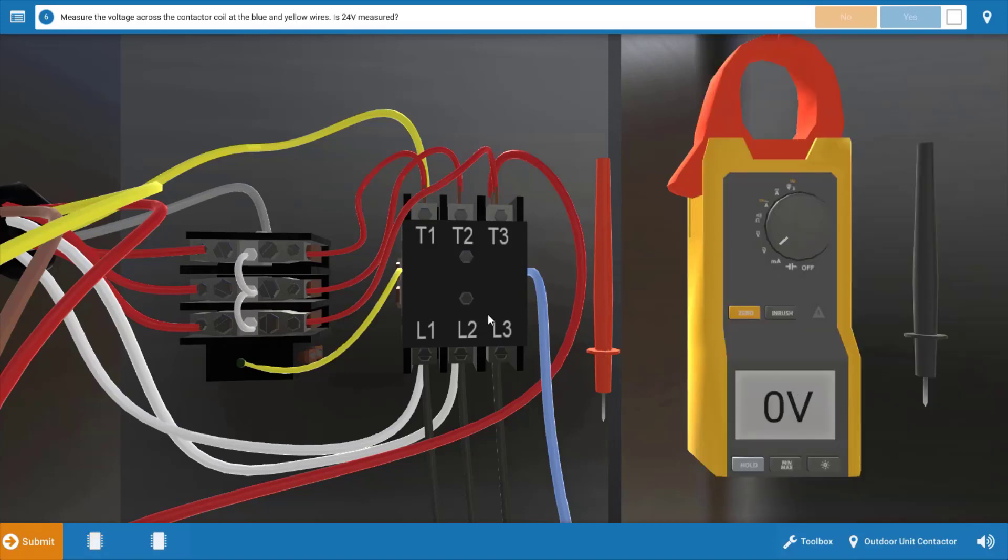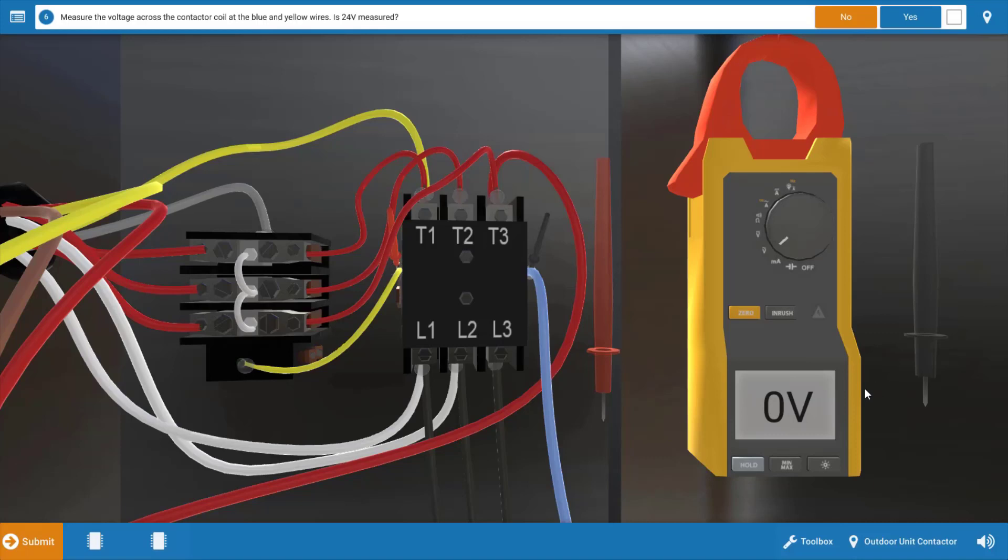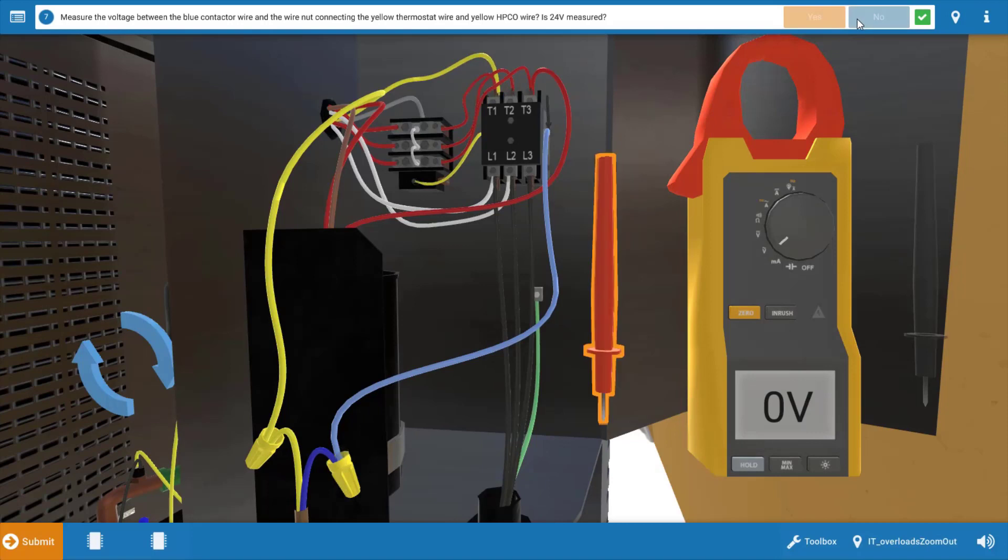We're going to start by measuring at the contactor coil. That seems to be the most logical place here. When we do that we can see we have zero volts at the contactor coil, which means the contactor is not our fault here. We've got something open in series to it, meaning one of those safety switches or possibly the thermostat is open.